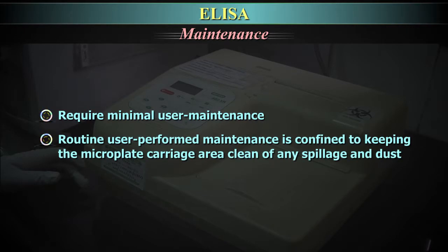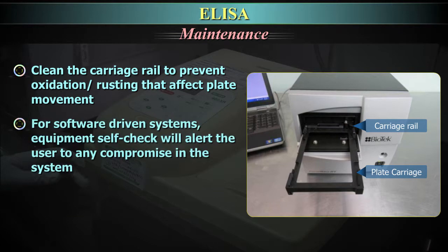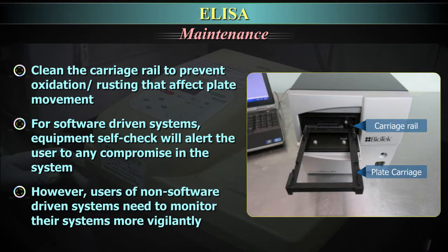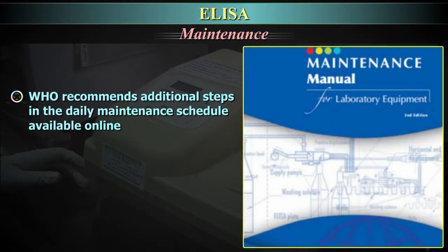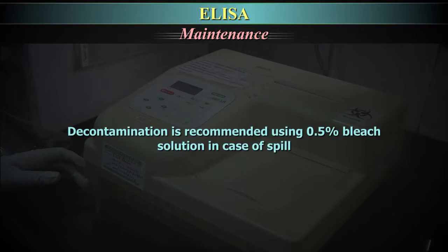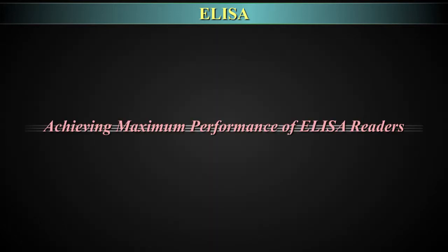Maintenance. ELISA readers require minimal user maintenance. Routine user-performed maintenance is confined to keeping the microplate carriage area clean of any spillage and dust. Clean the carriage rail to prevent oxidation or rusting that affects the plate movement. For software-driven systems, equipment self-check will alert the user to any compromise in the system. Users of non-software-driven systems need to monitor their systems more vigilantly. Decontamination is recommended using 0.5% bleach solution in case of spill, to achieve maximum performance of ELISA readers.